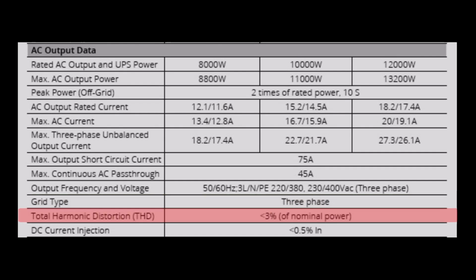Total harmonic distortion, THD, is less than 3% of the nominal power. What that's telling us is that harmonic distortion is something that occurs in electricity where there's an unbalanced electricity which interferes with efficiency and flexibility. And it's less than 3%, so it shouldn't be a problem. DC current injection: a little bit of DC current will get into the AC side, but it will be less than 0.5%, so that also shouldn't be a problem.